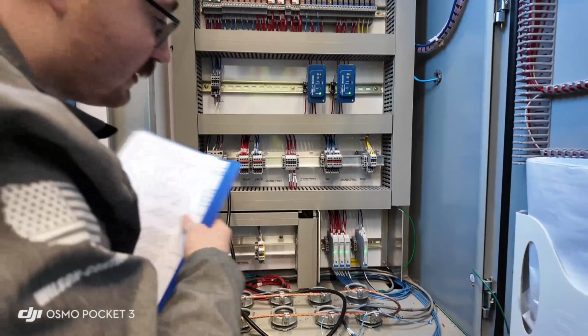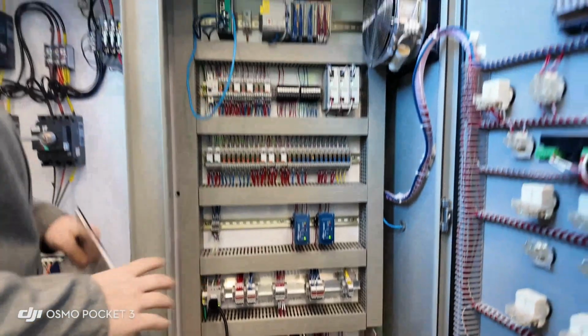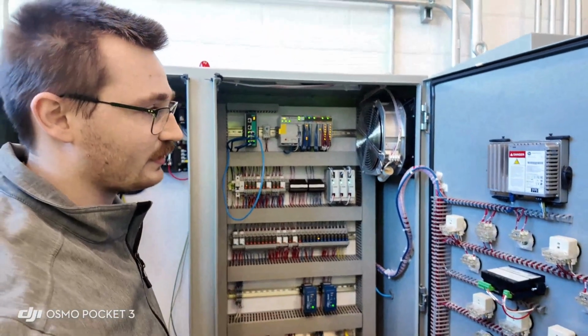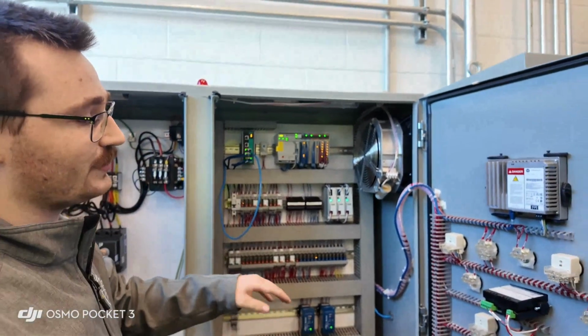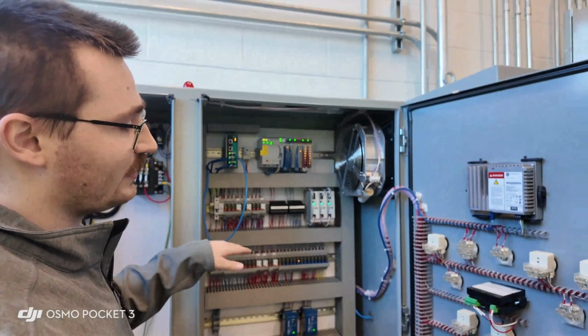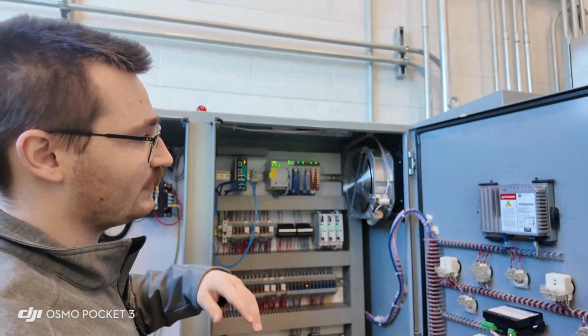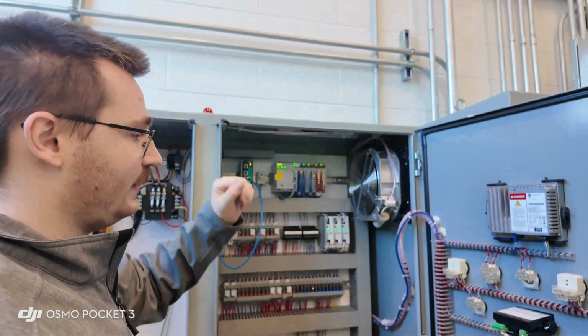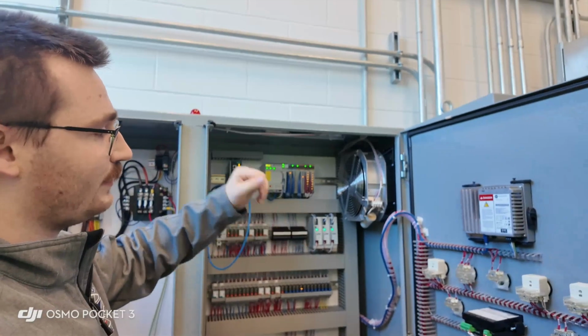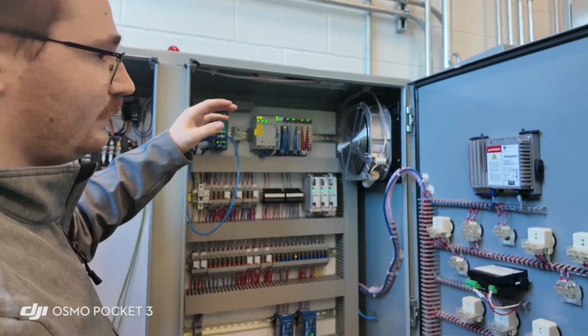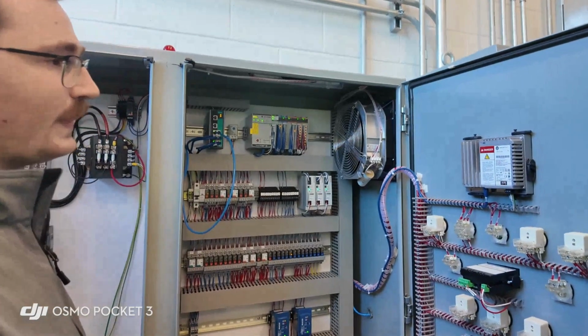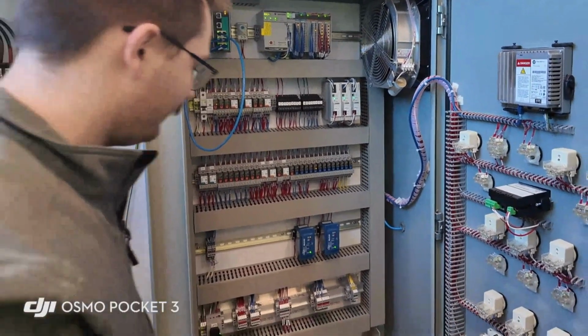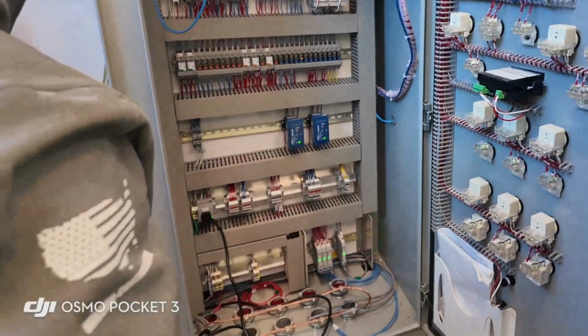It's a 5-float system. So you have your low, which is just an alarm. Then you have your low level, which is used to shut off your backup. You have your level set point 1 and level set point 2, so level set point 1 is going to start your first pump. When you reach level set point 2, you start your second pump. Then you have your high level alarm. So that's the 5-float, and then this one's just an intrinsically safe barrier for the 4 to 20 signal.